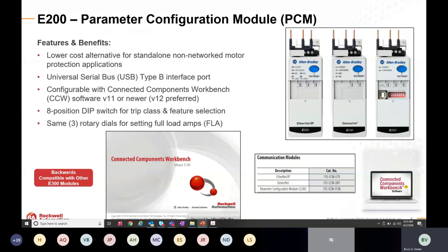Let's look at some features and benefits of the E200. It's another lower cost alternative to the higher end E300 for standalone, non-networked motor protection applications. The E200 is the image all the way to the right—you can see there's a USB Type B interface port you can connect to check and configure the device. Once you're done commissioning and configuring, you unplug it and the device continues to locally protect from an overload perspective.